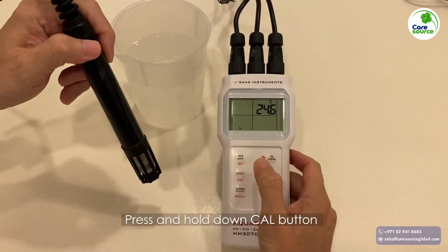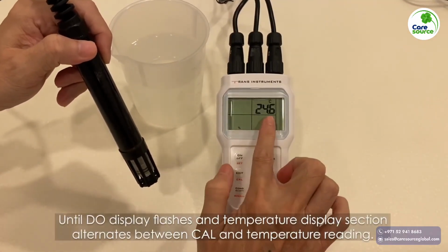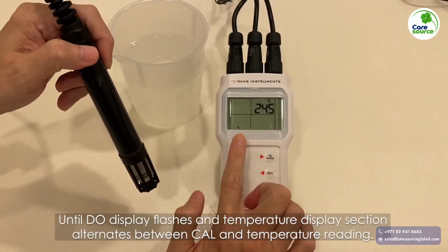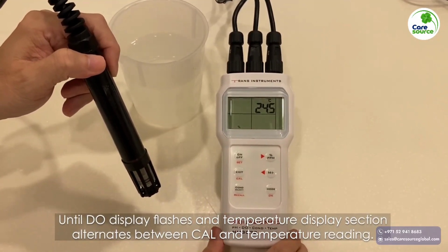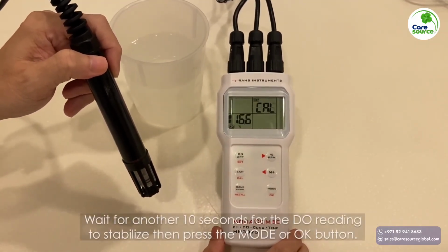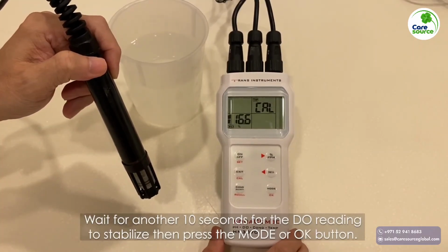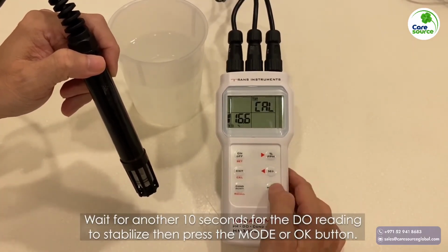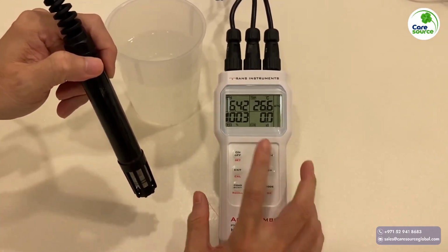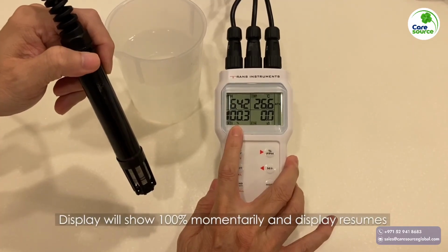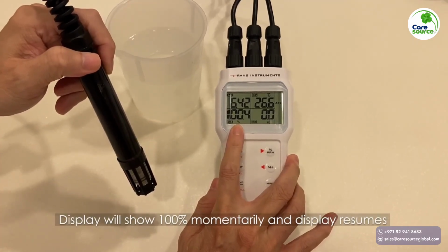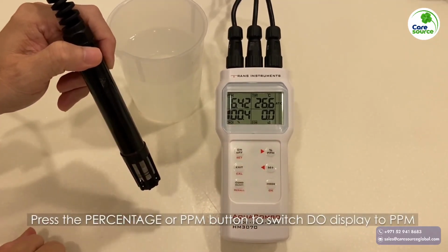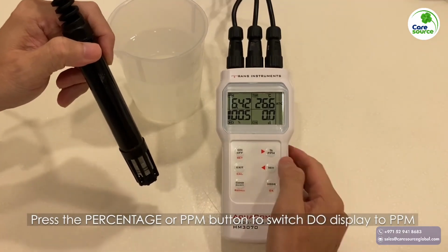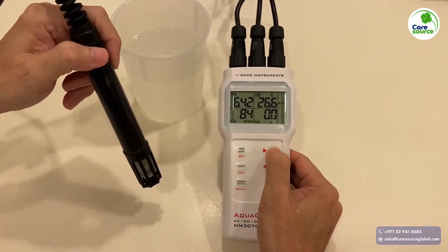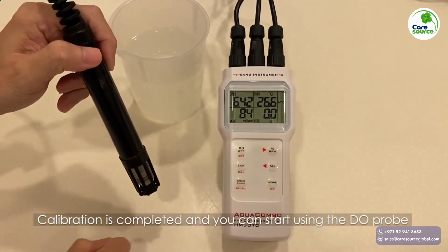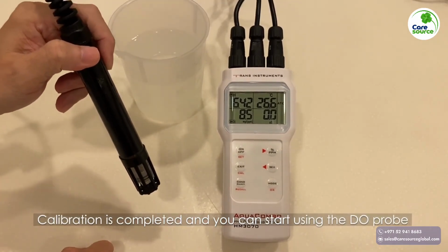Press and hold down the Cal button until the DO display flashes and the temperature display section alternates Cal and temperature reading. Wait for another 10 seconds for the DO reading to stabilize, then press the Mode OK button. The display will show 100% momentarily and the display resumes. Press the percentage ppm button to switch the DO display to ppm. Calibration is completed and you can start using the DO probe.